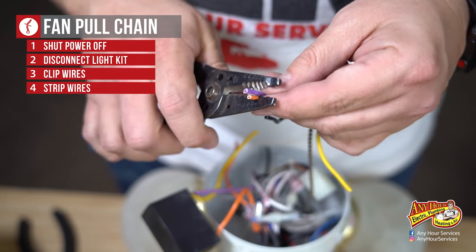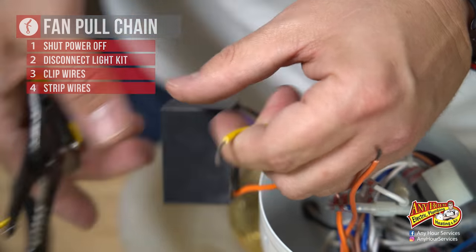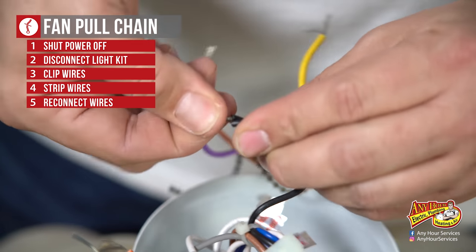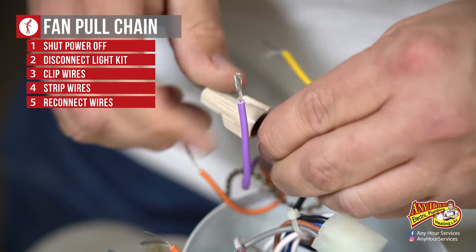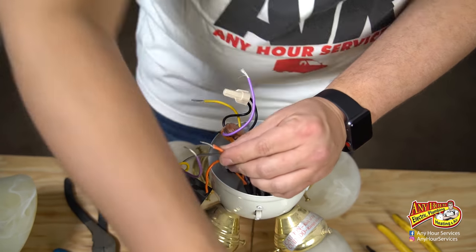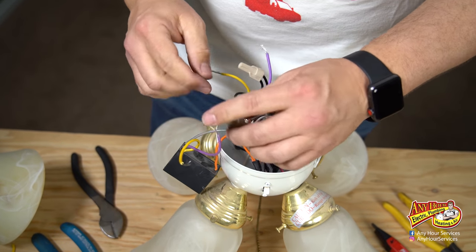Now I'm going to expose some of the wires — strip these back, same thing over here. You only need to strip them back about half an inch, just enough so that you can twist them together with the other wires. Then we're going to go color to color: orange with orange, purple with purple, yellow with yellow, black with black. Twisting the wires together helps them have less likelihood of coming apart and shorting out. Wire nuts protect them from touching other things around the housing that would be bonded to the grounding system and would cause a short.